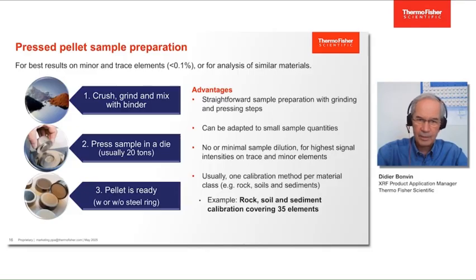Maybe the dilution is brought by the binder, but generally we will never use more than 10% binder, in the cases where the powder does not agglomerate well, which means we get the highest signal intensities on the trace and the minor elements. The drawback is that the calibration generally can only be done for one type of sample species, like for example, one calibration for cement, one calibration for slags, another one for limestone.